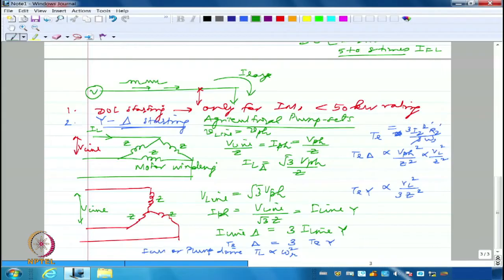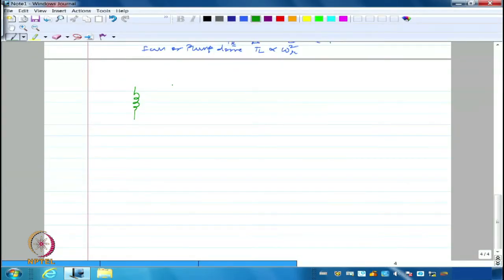Not a big deal. And generally there will be a time delay. It will be in star for probably 0.5 seconds, 0.7 seconds, and after that it will automatically switch over to delta. So when that happens, both ends of the winding should be brought out. I hope you understand. If I am going to have A, B, C three-phase windings, I'm going to have this as A, this as B, and this as C. So if I want star, I have to actually have contactors here and contactors here.